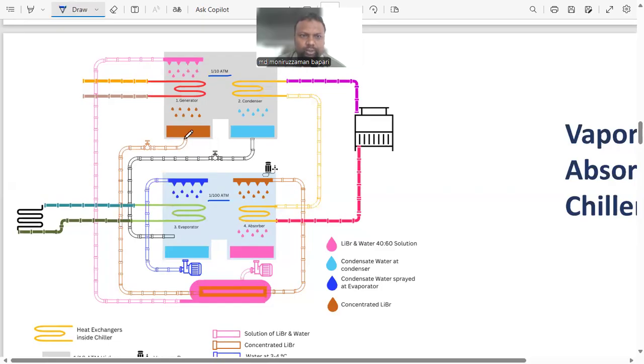And if you see, there are two different types of pipelines connected here. Some pipelines are connecting the two chambers, higher pressure and lower pressure chamber, like this one, the black one, and the gray one, and the pink one. They are connecting the top chamber with the bottom chamber. And there are pipelines which are external. They come in and go away, like this pipeline. This is a pipeline actually coming from fan coil unit or air handling unit. Hot water coming in, chilled down, and going out. And there is a pipeline coming from the cooling tower. Cool water is coming down and comparatively hot water is going out to the cooling tower here.